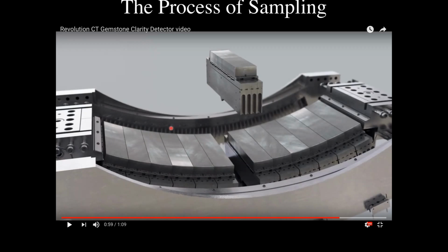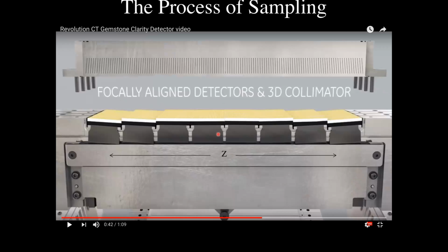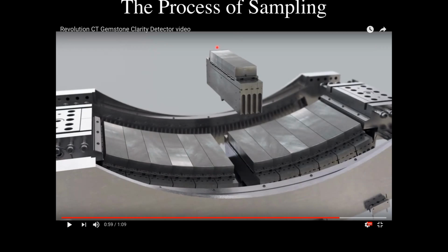So this is like a chunk out of the donut, right? A big 45-degree slice out of the donut. And then the detector elements themselves plug in here as units. So they're replicants, and they just plug in. When you look inside one of these units, right down here is the detector. You can see the little detector elements along there. This is an anti-scatter grid, which we'll talk about a bit, but there's the detector elements along there.